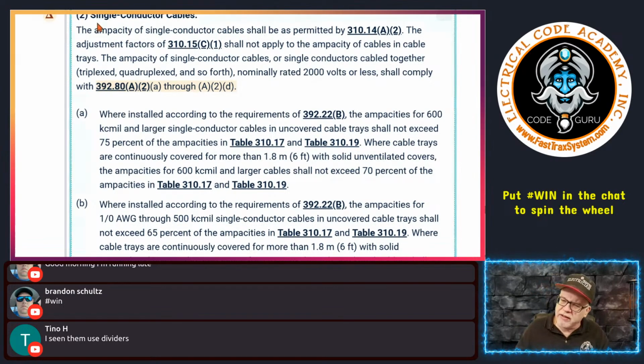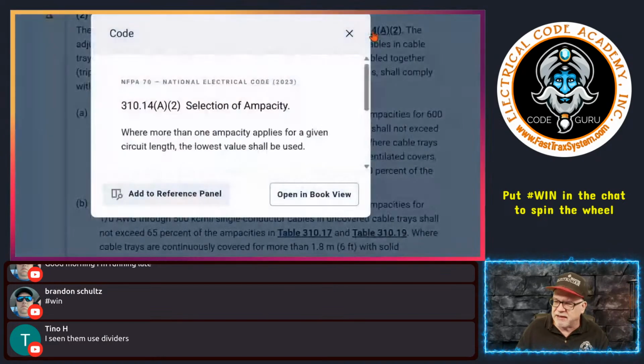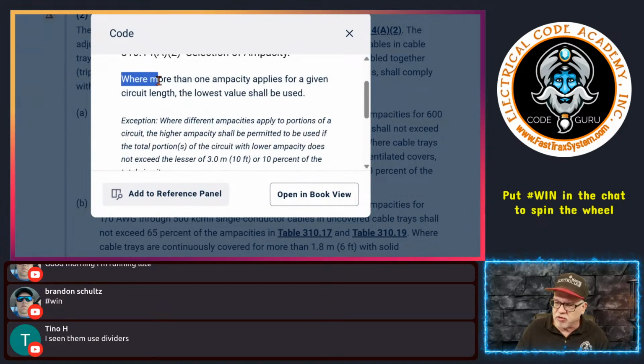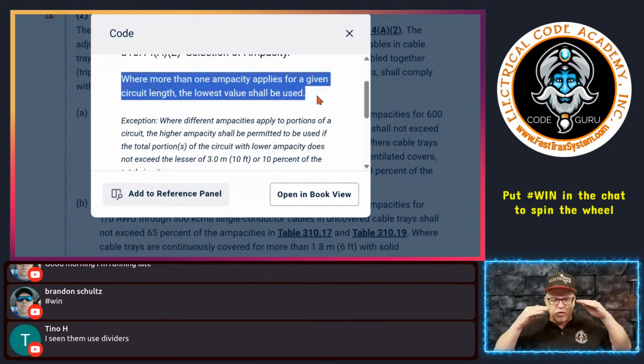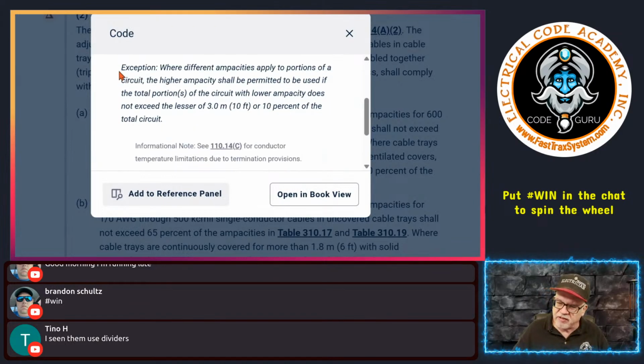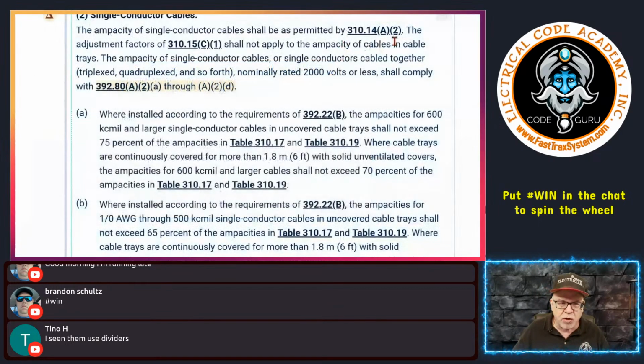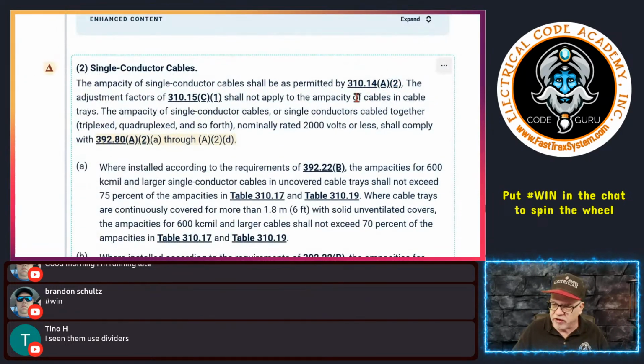Okay, so anyway, the ampacity of single conductor cables or single insulated conductors for the most part here shall be permitted by 310.14(A)(2). And if I click that for you, again, this is just talking about that rule where, if you have 2 different values, you use the lower one. But this reminds you that the exception is in play because it doesn't remove the exception, okay? So this is still in play when it comes to cable trays. That's a good thing, right?